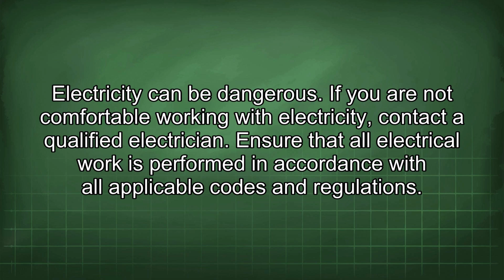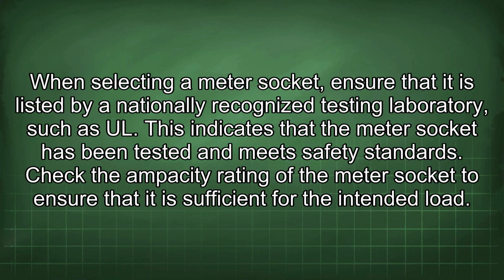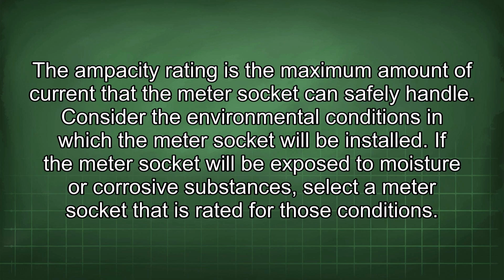Ensure that all electrical work is performed in accordance with all applicable codes and regulations. When selecting a meter socket, ensure that it is listed by a nationally recognized testing laboratory such as UL. This indicates that the meter socket has been tested and meets safety standards. Check the ampacity rating of the meter socket to ensure that it is sufficient for the intended load. The ampacity rating is the maximum amount of current that the meter socket can safely handle.